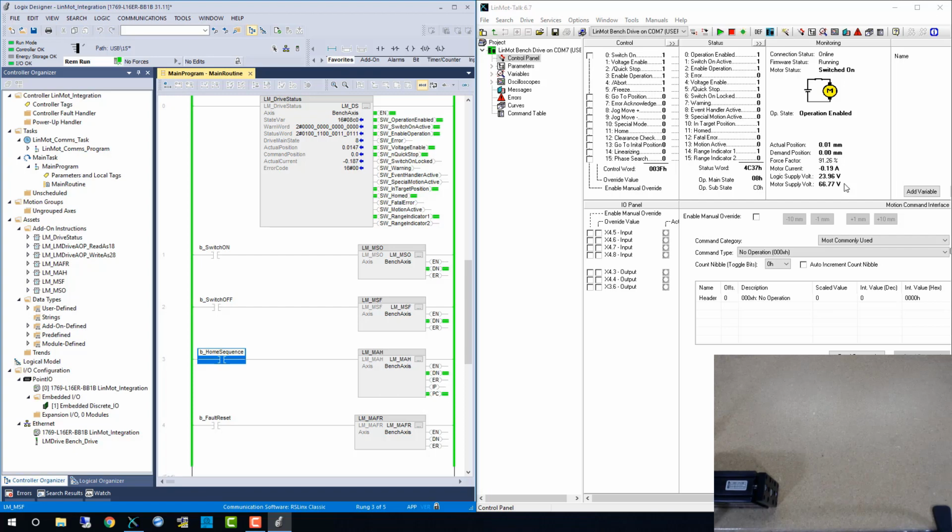From here, we'll test the error acknowledge bit. I've simply switched off the 72 volt supply, and as capacitors bleed down, we'll go into a warn state, and then an error state as we go below 40 volts.